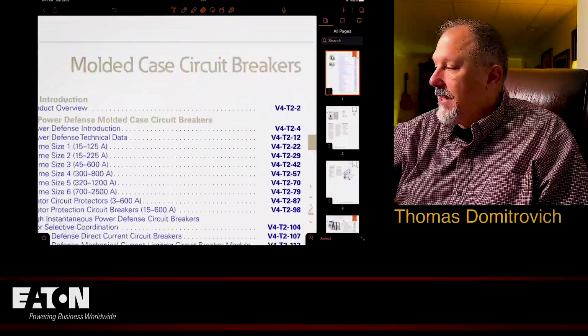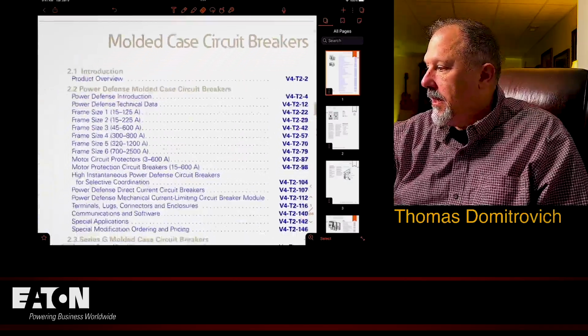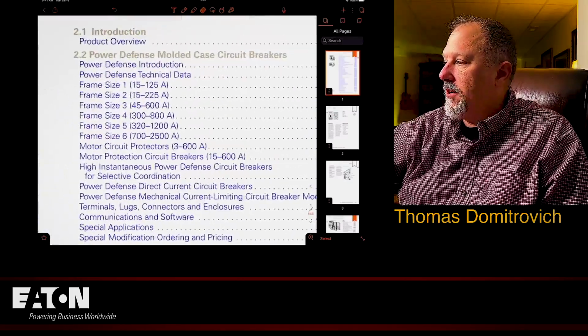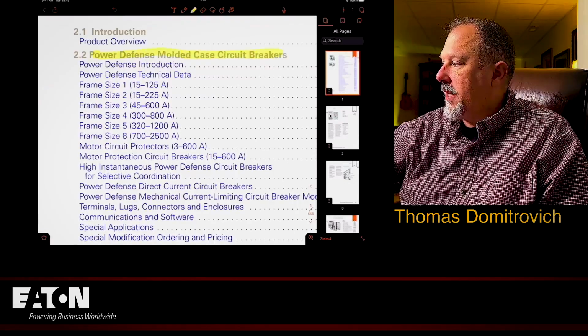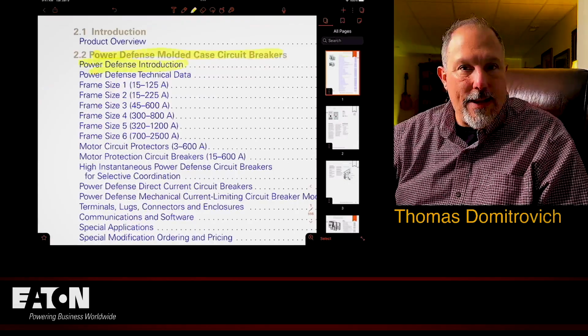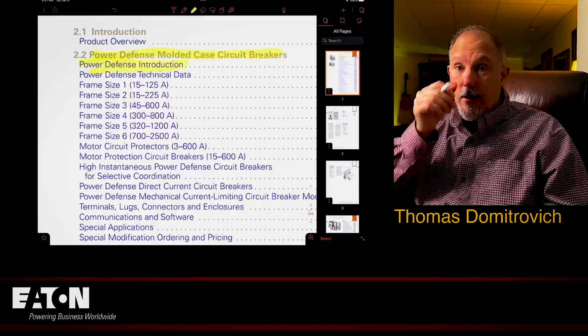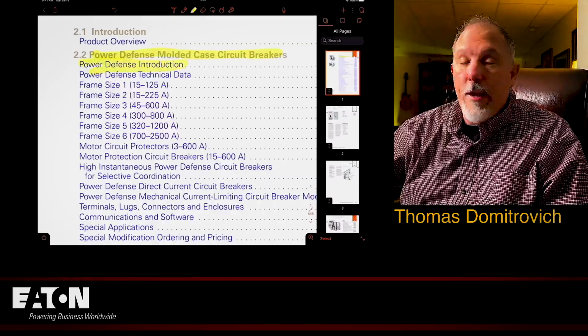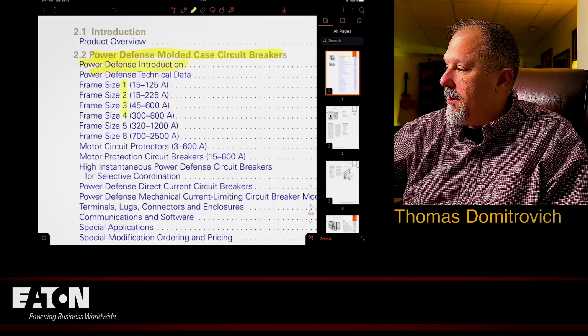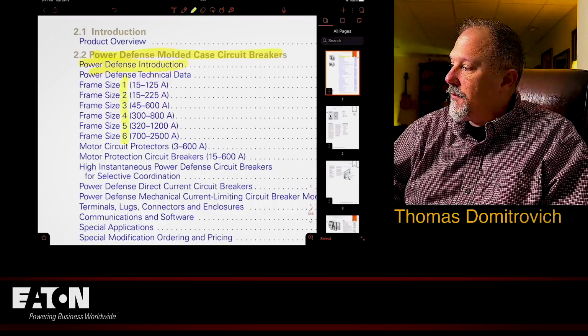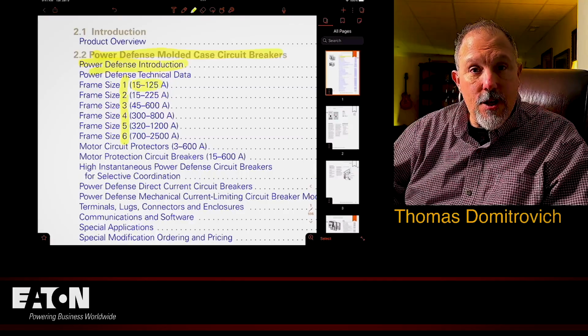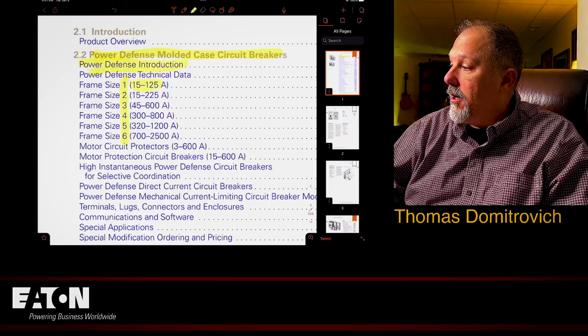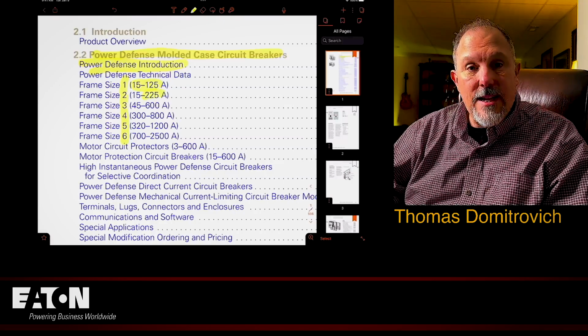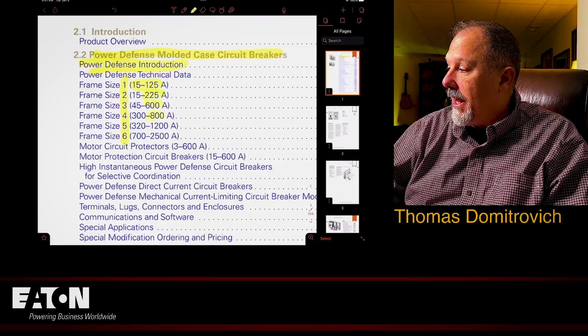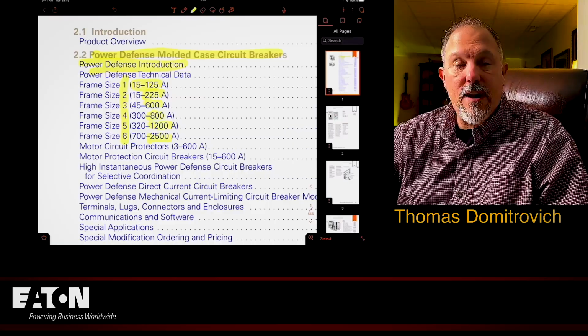This is our molded case circuit breaker catalog. And you'll notice that the Power Defense molded case circuit breakers, that's our latest circuit breakers that are on the market. We have 6 frame sizes. We have 1 through 6. Each frame size has a range of currents for the size of the breaker. The size 1 goes up to 125, size 2 to 225, size 3 to 600, then 800, 1200, and 2500.